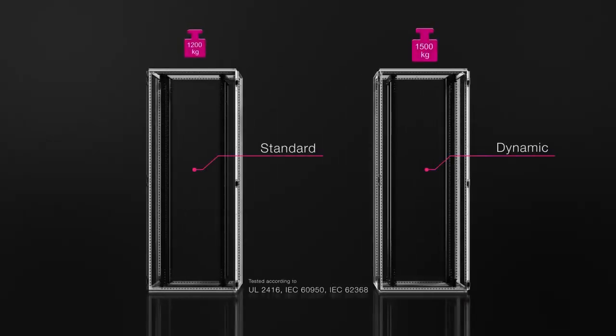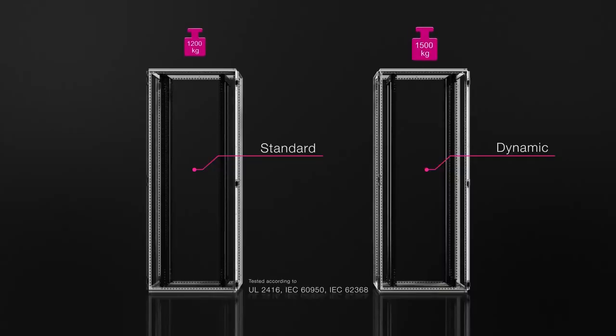The packaging density in IT racks is constantly increasing. Do you also have higher load requirements for your IT rack in a data center? With the new VXIT, we have two product lines, standard or dynamic, with two different load capacities. The two product lines are based on different material thicknesses of the 19-inch levels. With a material thickness of 2.0 mm, the standard product line is especially suitable for the main applications. It can be loaded up to 1500 kg and, according to UL 2416, up to 1200 kg.